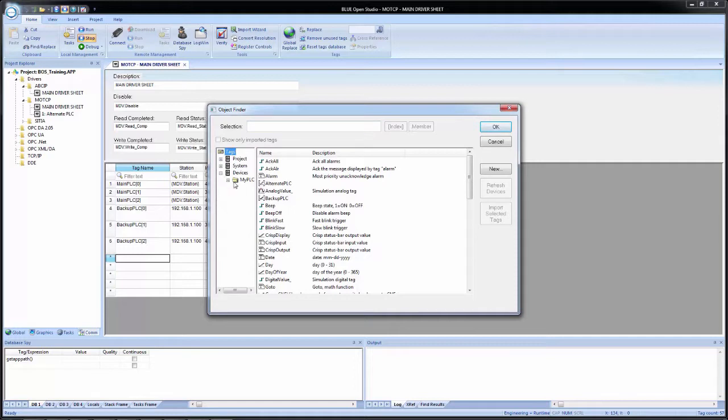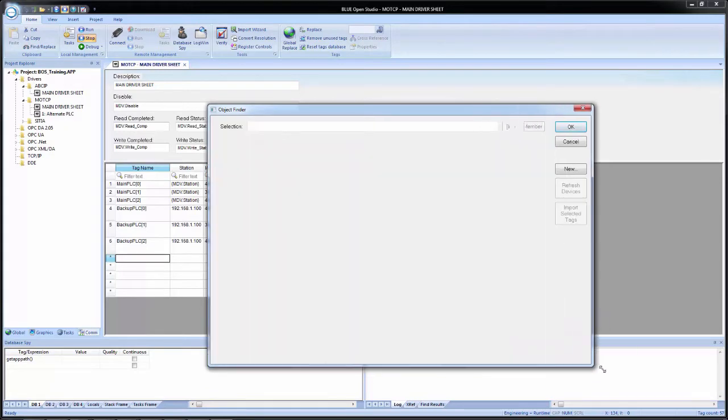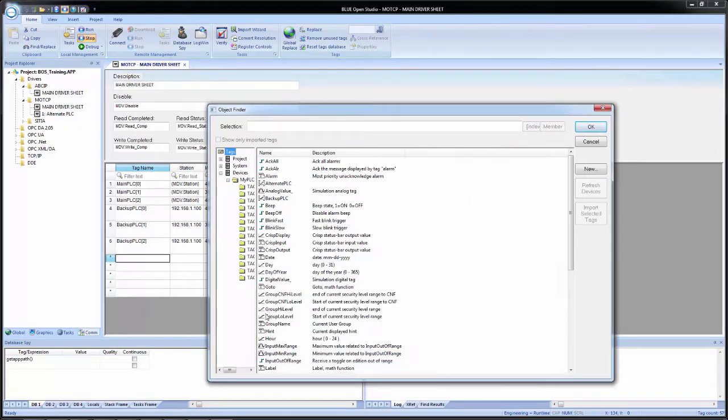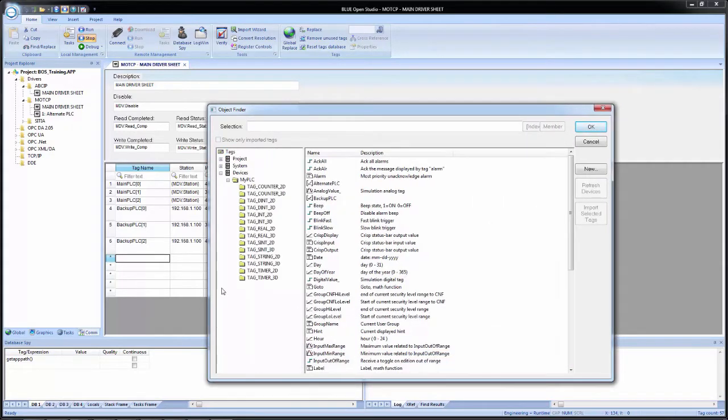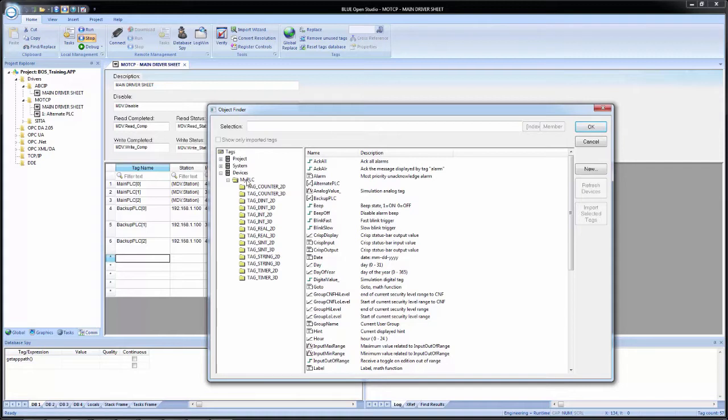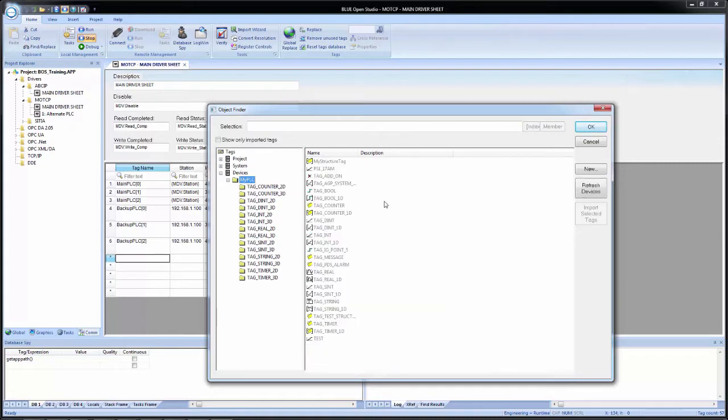If I expand this, I see my PLC. If I expand this again, let me drag this out so we can see a little bit more. We now see I have my groups of tags that have been referenced. This is not a list that's populated inside of Blue Open Studio. It's referencing the tag list from that L5K file. If I was connected to an actual PLC over Ethernet, it would simply reference the tag list from there. So in this case, I can browse it like I can any of the project tags.